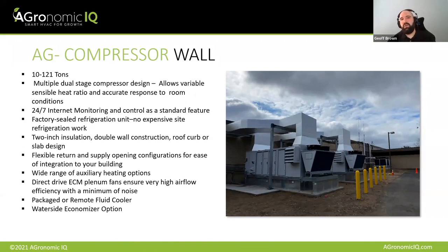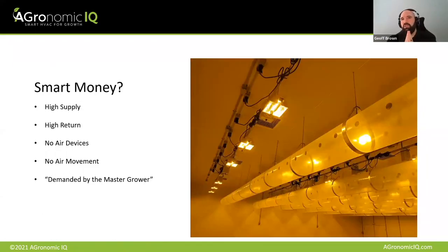But here's an example of a grower that ultimately just didn't choose the right partner to build their building. What we've got here is the top of a grow room. This is a flower room, and this grower has elected to use disposable ductwork with the intent of throwing it out between every flower cycle. They've got typical double end discharge at the top of their room. They've got high supply and high return. These return grills are in the ceiling, and they've got their supply up high. Obviously, that ductwork isn't going to be getting air anywhere useful.